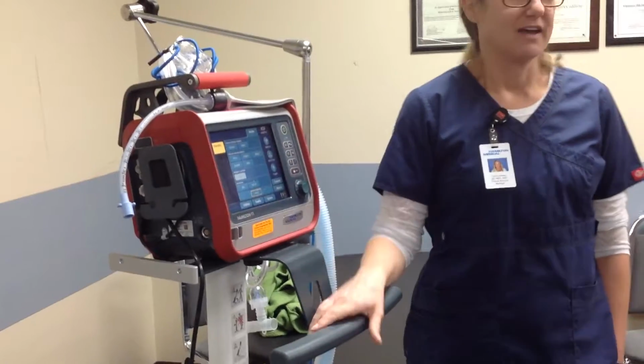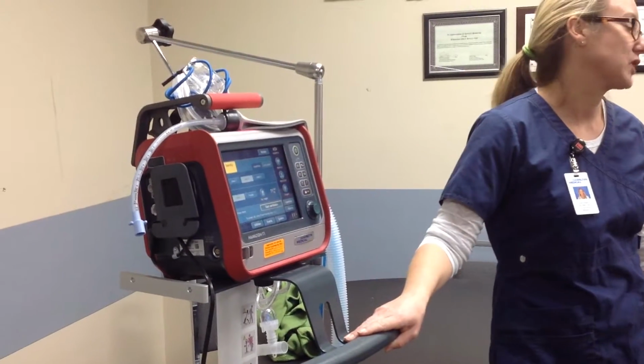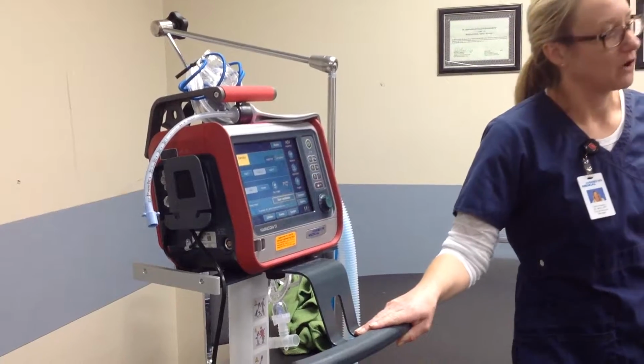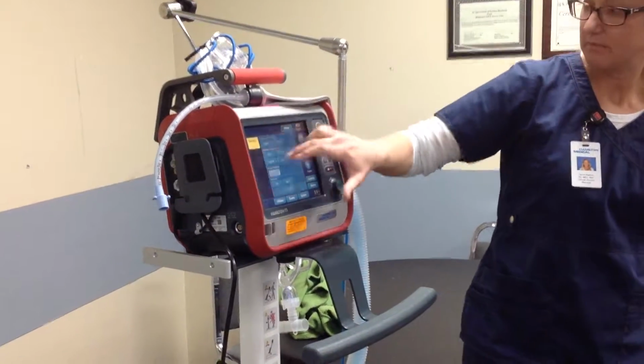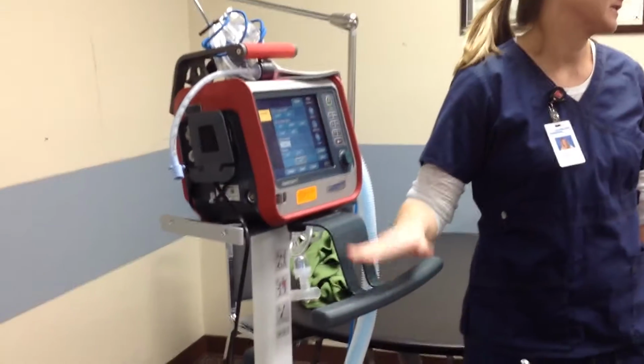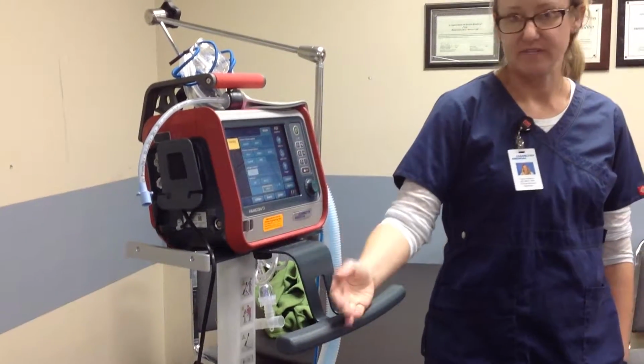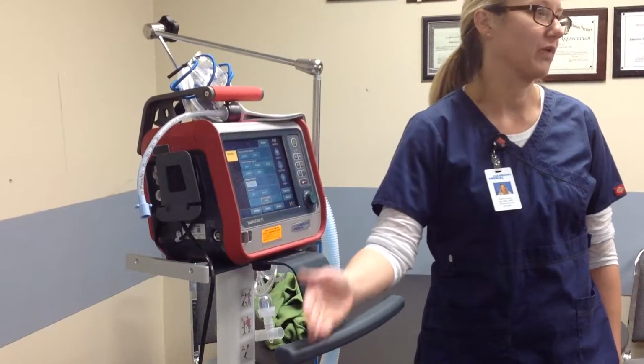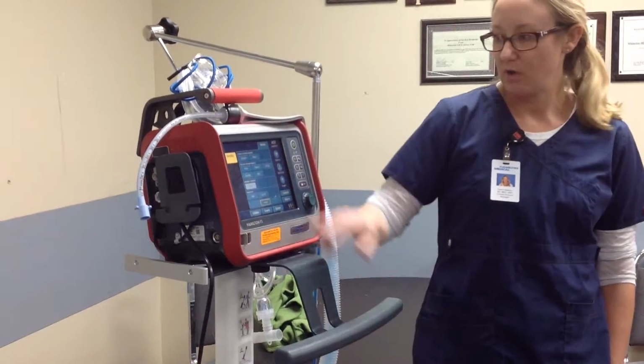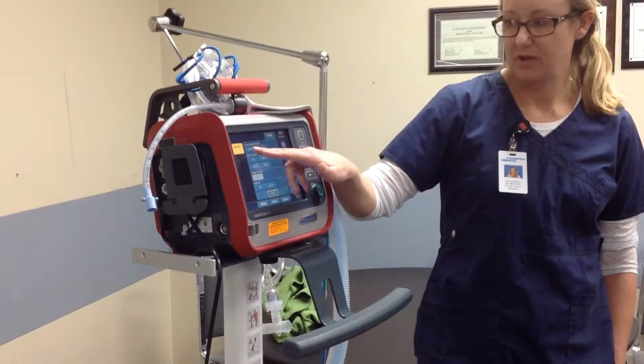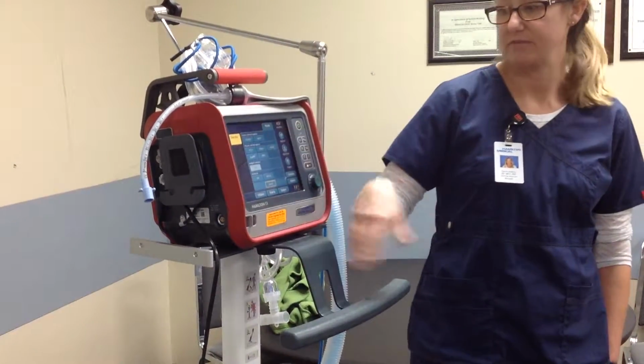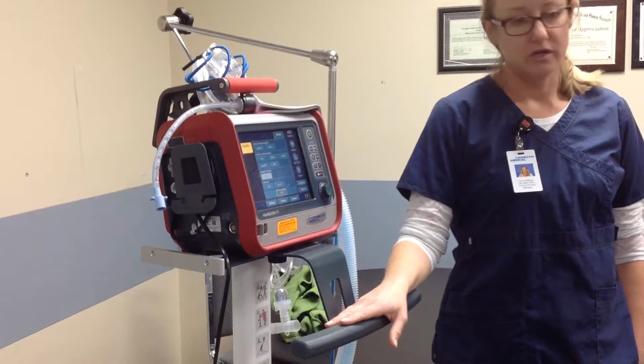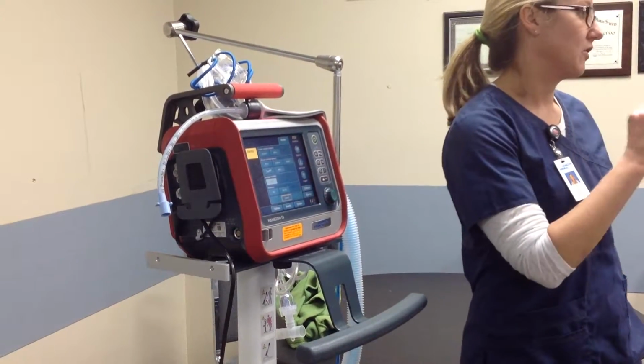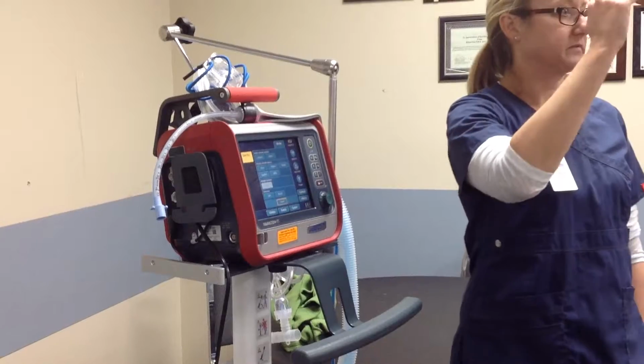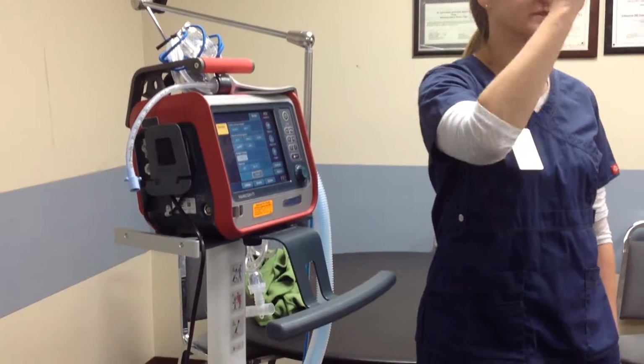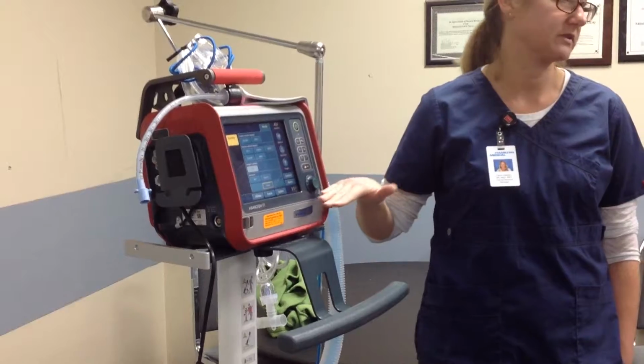So if you're familiar with pressure regulated volume control or volume guarantee, that's really what these modes are. SCMV, synchronized continuous mandatory ventilation, that's VC plus or volume control plus, or pressure regulated volume control. If you ever use these two modes, SCMV plus is assist control volume control, SIMV is the synchronized version of that, you're going to notice that if you dial in your patient's targeted volume, it's not going to immediately get up to that volume. It's going to take steps to get up to that volume, and it's a safety feature that's built into the ventilator.